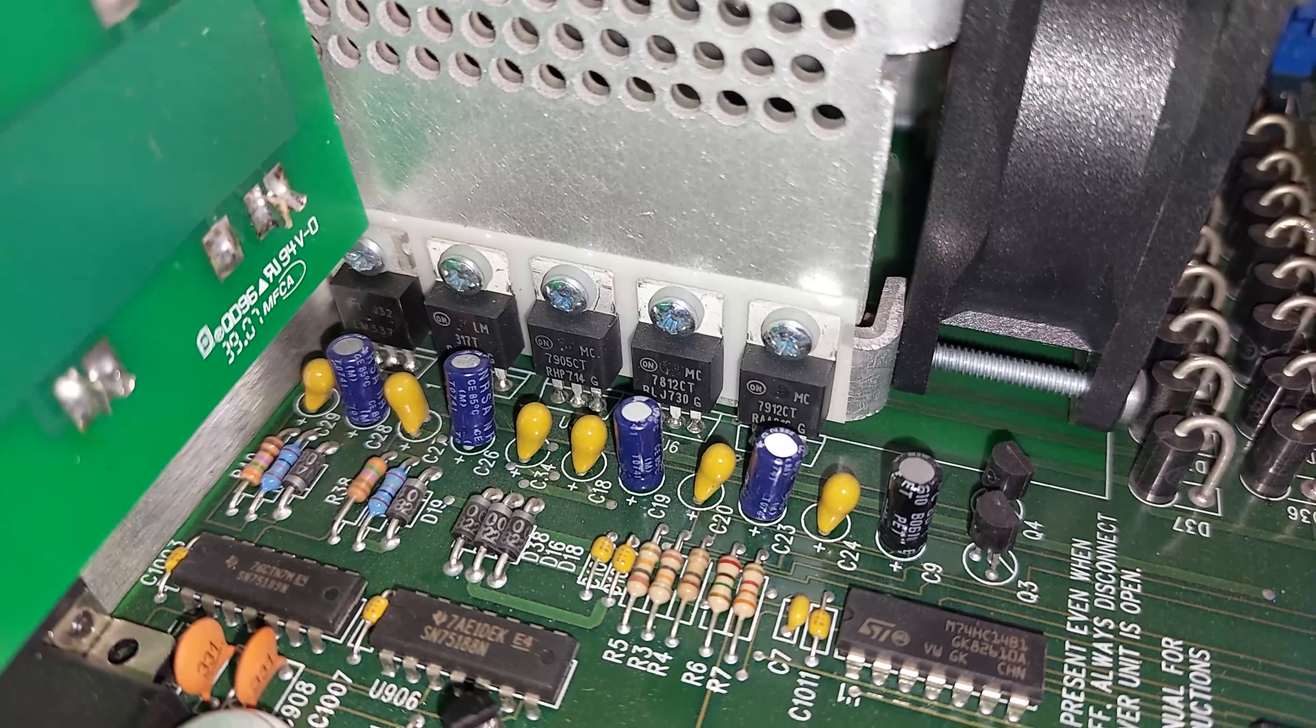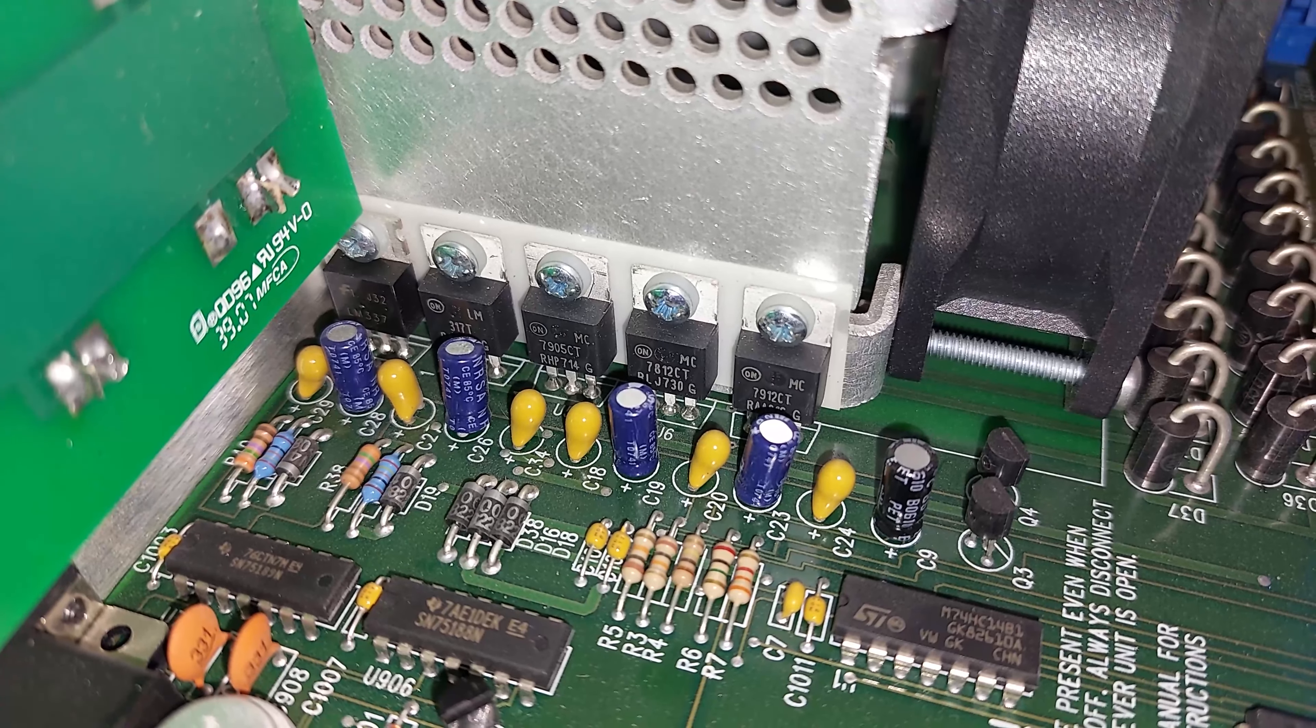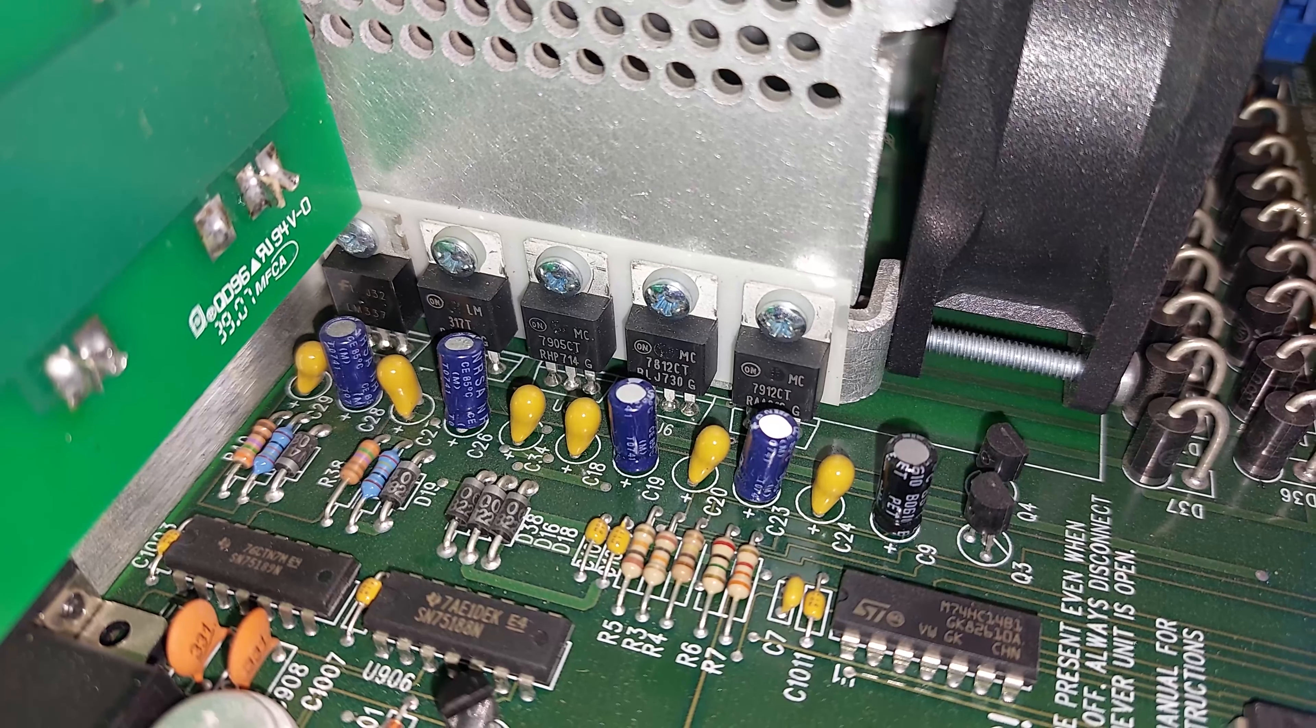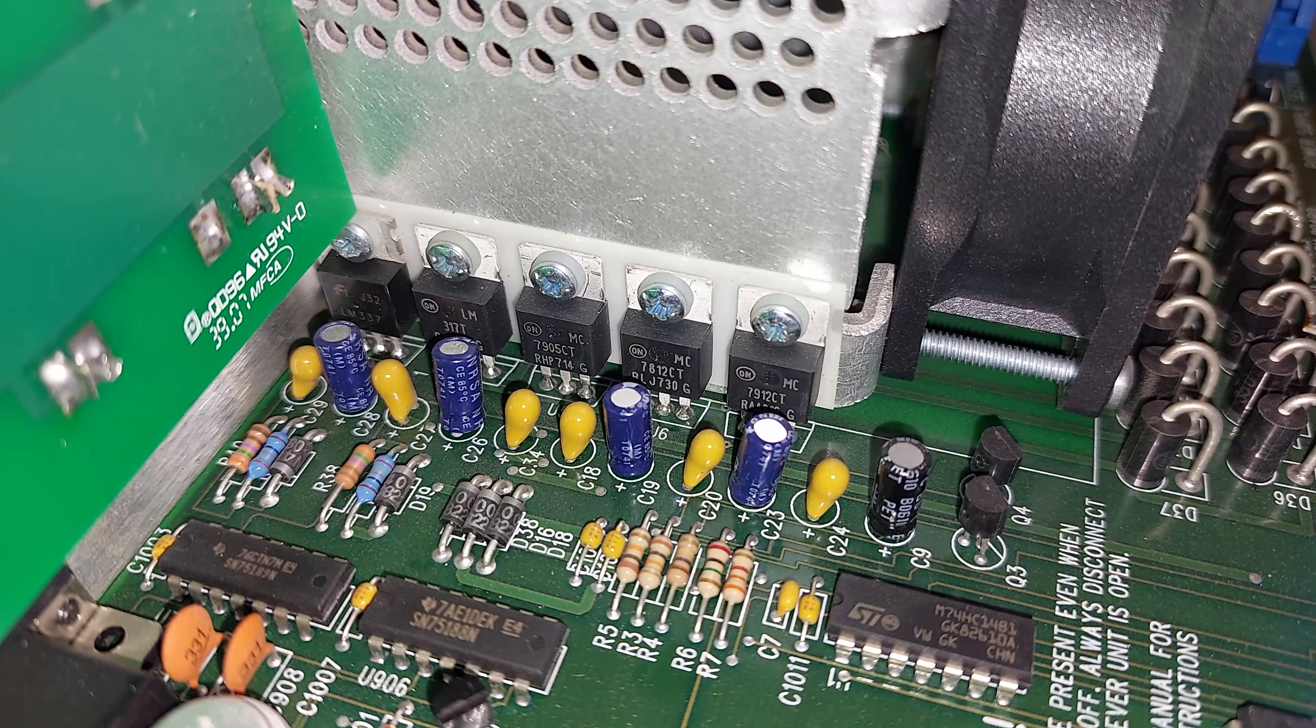The regulators generate the various regulated rails for the rest of the device. There is a plus/minus 12, a plus/minus 5, and a plus/minus 20.